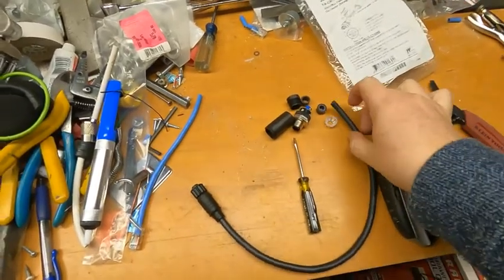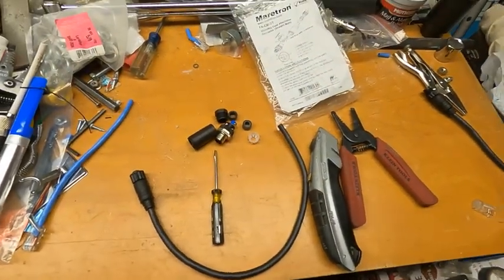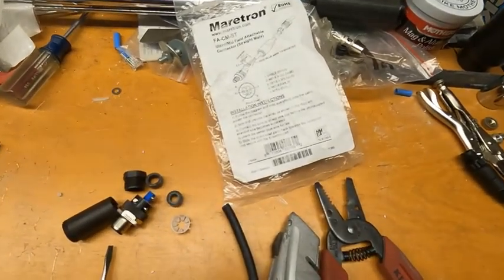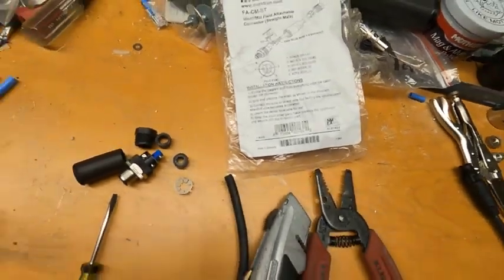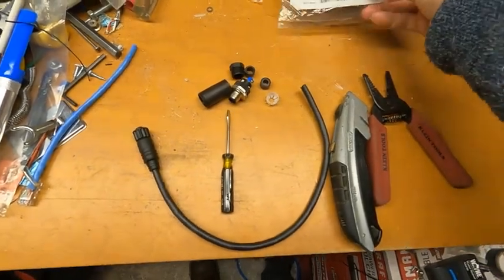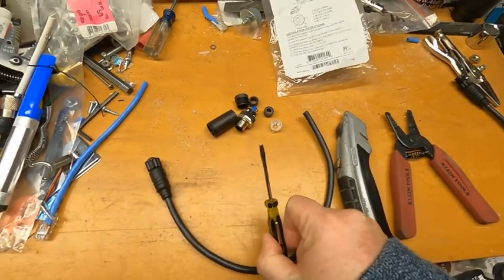What I have here is a field connector made by Maretron. On the bag it does give you some instructions. I actually don't follow them because the main difference is where it says in number 4, leave the center blue wire for last — I actually don't agree with that. It's a lot easier if you do it towards the beginning. Tools that you might need are wire cutters and strippers, a razor blade knife, and a small flathead screwdriver.